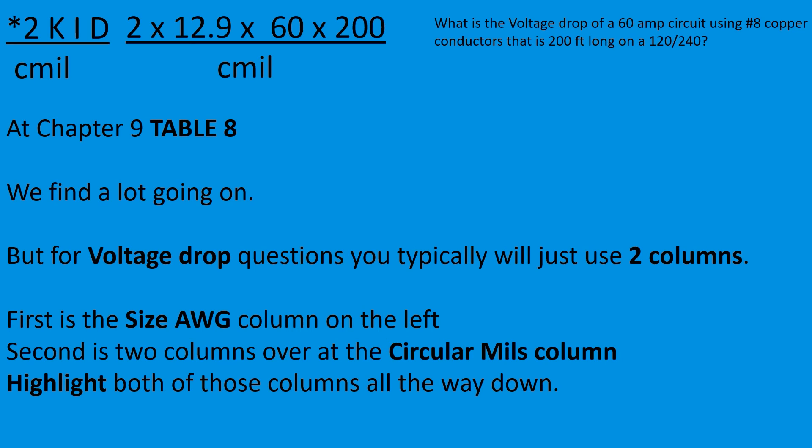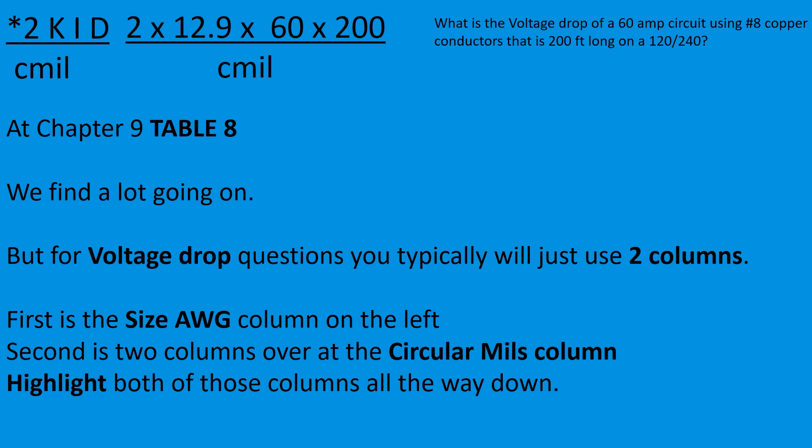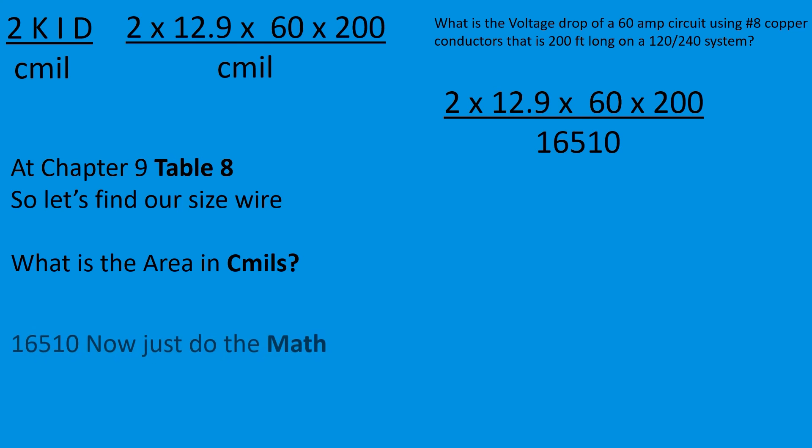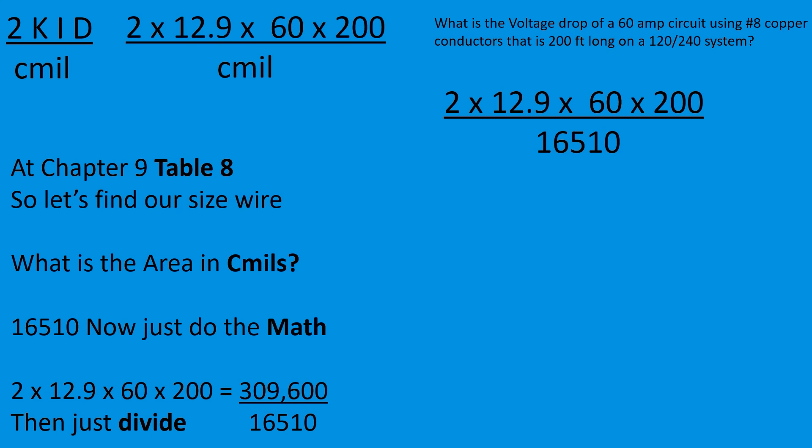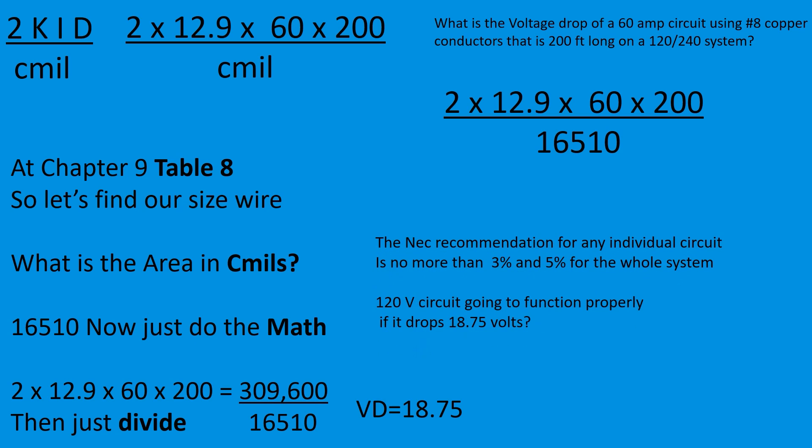Okay, so Chapter 9 Table 8. We find our size wire, we slide over to the area in circular mils. Okay, now we just do the math. So we take 2 multiplied by 12.9, multiplied by 60, multiplied by 200, equals 309,600. Then we just divide. You divide 16,510 into 309,600 and we're going to get a voltage drop of 18.75.